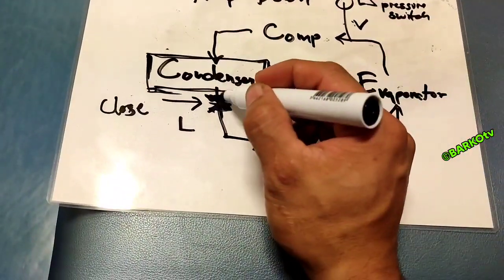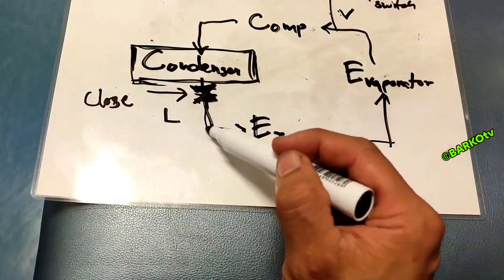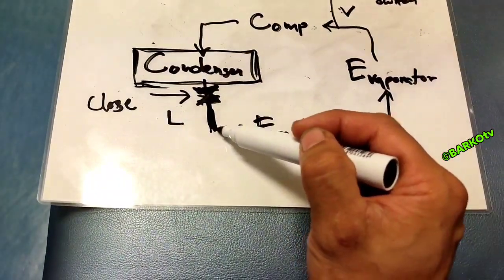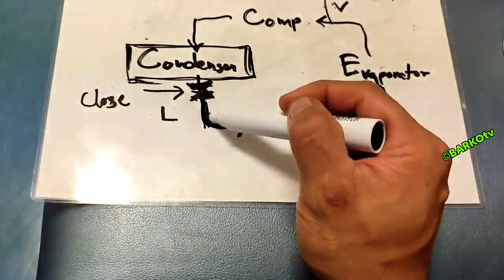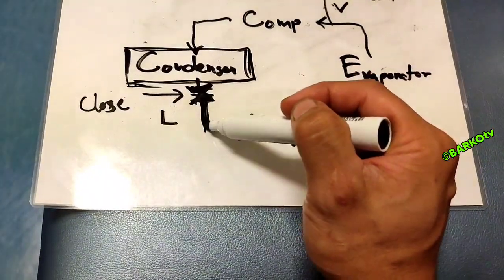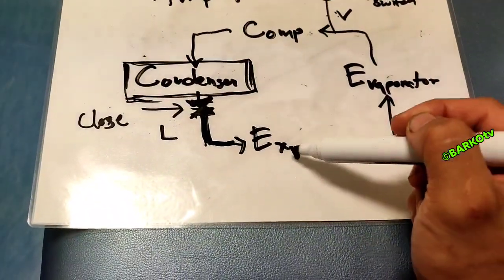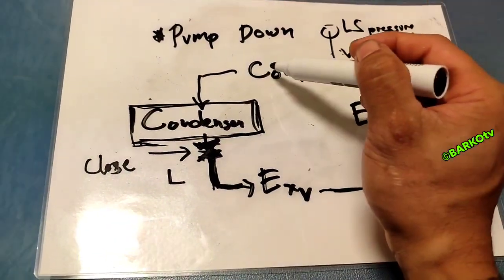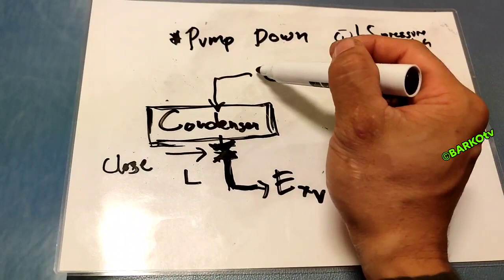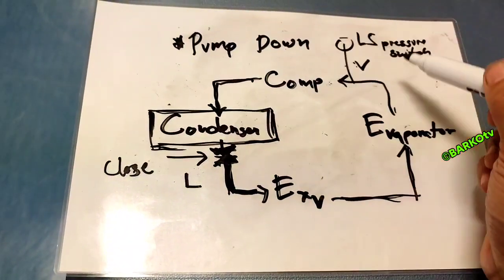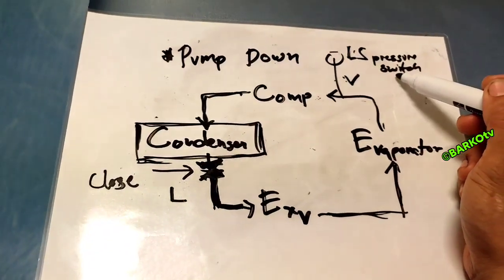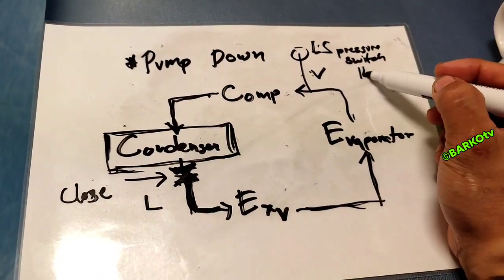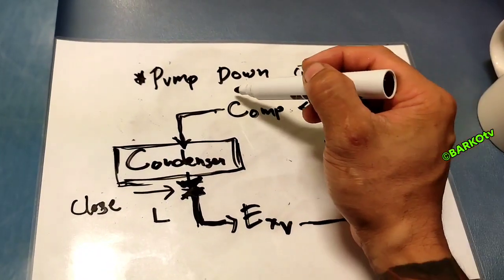Starting with your isolating valve — this one — if you close this valve, you start pumping down. That pipe goes to the expansion valve, then to the evaporator, then the suction brings it to the compressor, and then it goes to the condenser. The refrigerant starts collecting in the condenser.